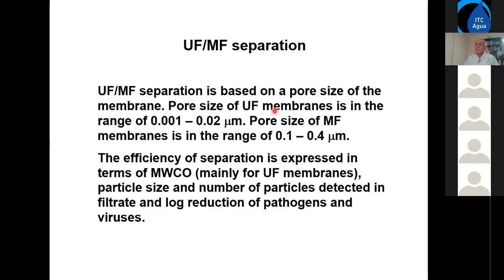In ultrafiltration, the pore size is in the range of 0.01 to 0.02 micron. Microfiltration is 0.1 to 0.4. However, it has to be said that both membranes foul during startup operation because we operate at 100% recovery, there is no cross flow. So regardless if this is an ultrafiltration or microfiltration membrane, they plug immediately, and the pores actually act like an ultrafiltration membrane. So based on diffusion, almost all the pores are blocked very shortly after startup of operation.